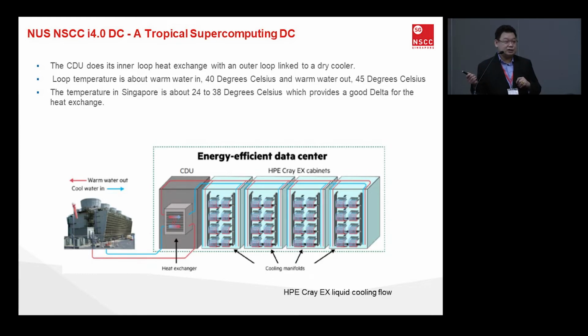with the CDU itself. Now this dry cooler works in Singapore because even if the temperature of the water that goes out into the system is about 40 degrees, Singapore rarely hits 40 degrees. So as long as we have enough delta T, the water in the system will cool down, and hence we save on cooling. Because let's be very honest, running a supercomputer is very power intensive and cooling intensive. So we are trying to reduce our operating costs as much as possible so that we can provide the users a value for money system.